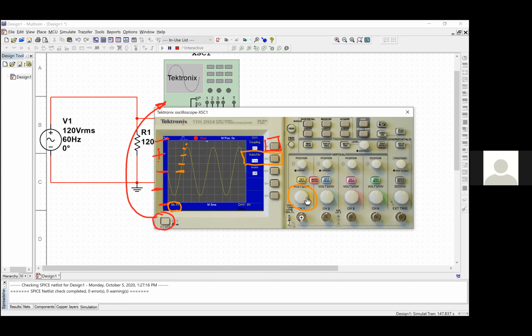And E peak is equal to E max. Please take note that the oscilloscope doesn't have anything that is called E peak. That language doesn't exist on the oscilloscope. The way that the oscilloscope is going to display it is called Emax.